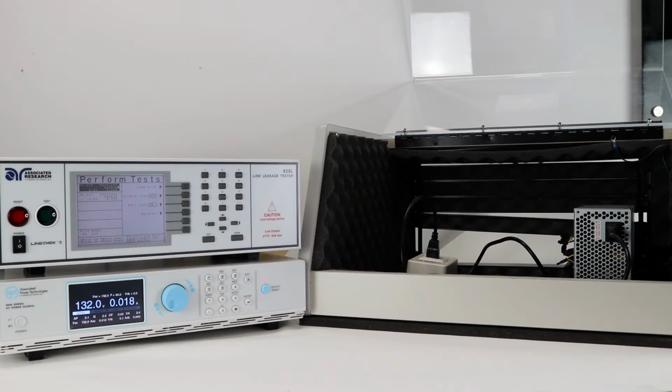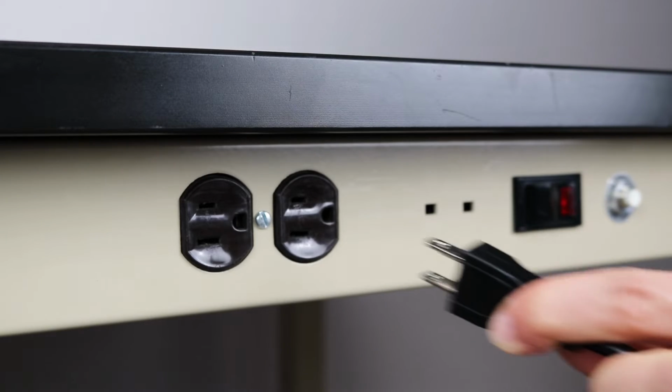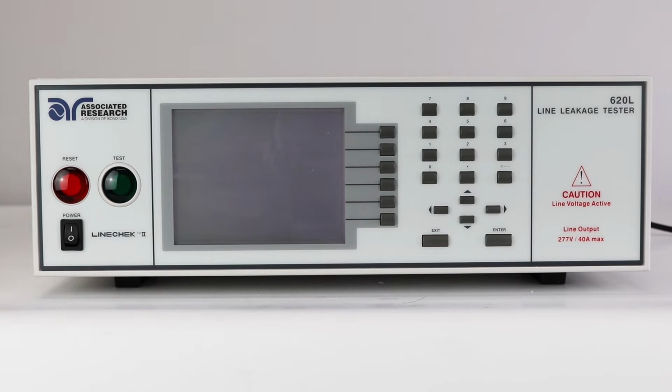This allows the user to wire the instrument to the doors of the DUT enclosure. This is a safe workstation best practice. Connect the power input plug into its socket on the rear panel of the instrument. Connect the male end of the plug to the outlet receptacle. Turn on the power switch located on the front panel of the linechek.